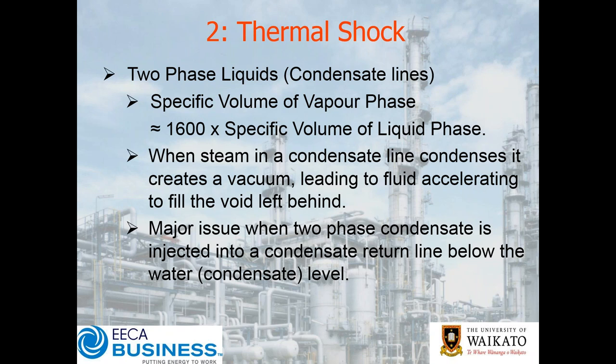In a condensate system, the specific volume of the vapor phase — when that condensate flashes off back into the vapor phase — is about 1,600 times the volume of the liquid phase. The actual number varies depending on pressure, but by and large it's over three orders of magnitude — that's a very big change. To put this in perspective: one litre of condensate flashes into 1.6 cubic metres of steam or vapor.